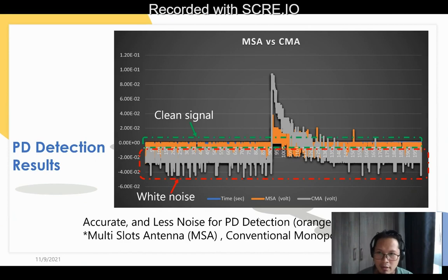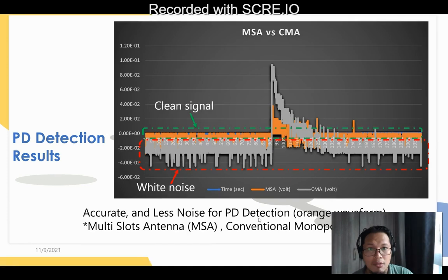Right. When we compare the PD detection results, the orange color and the gray color. Gray is the conventional antenna, whereas my proposed antenna is producing a clear, clean, better signal with good PD detection. Therefore, it produces accurate detection with less noise, especially the orange waveform, compared to the monopole antenna currently used by the reputable manufacturer. All right, this is the design that is used at industry level.